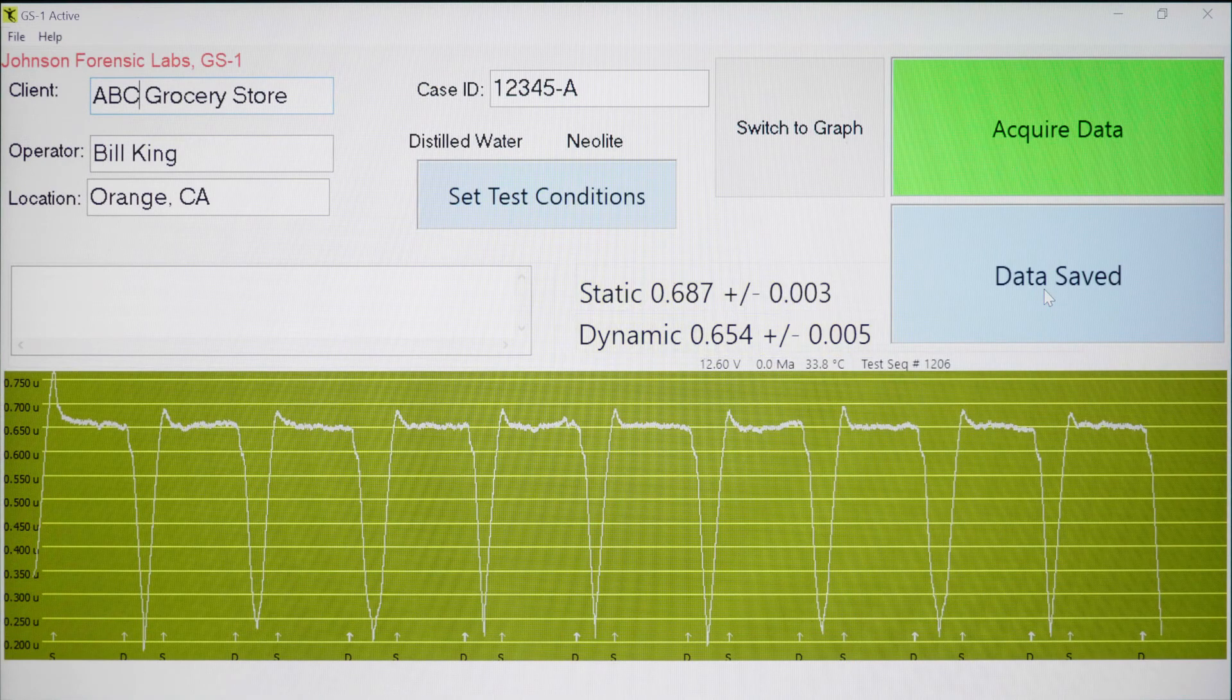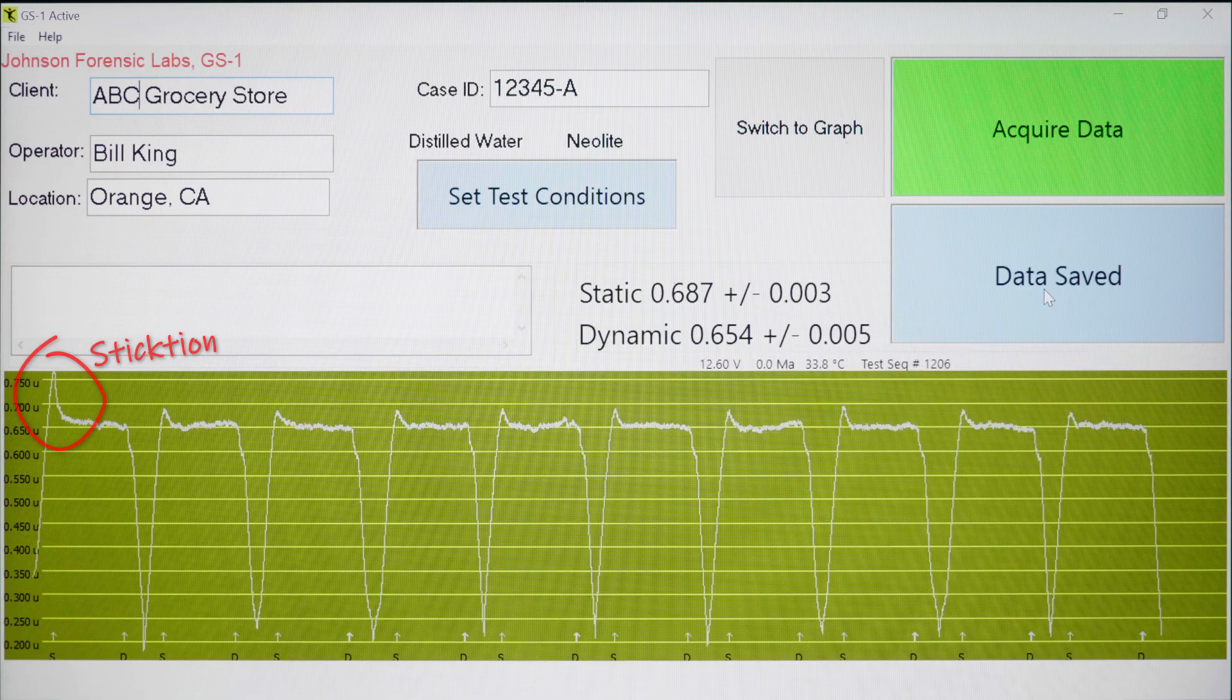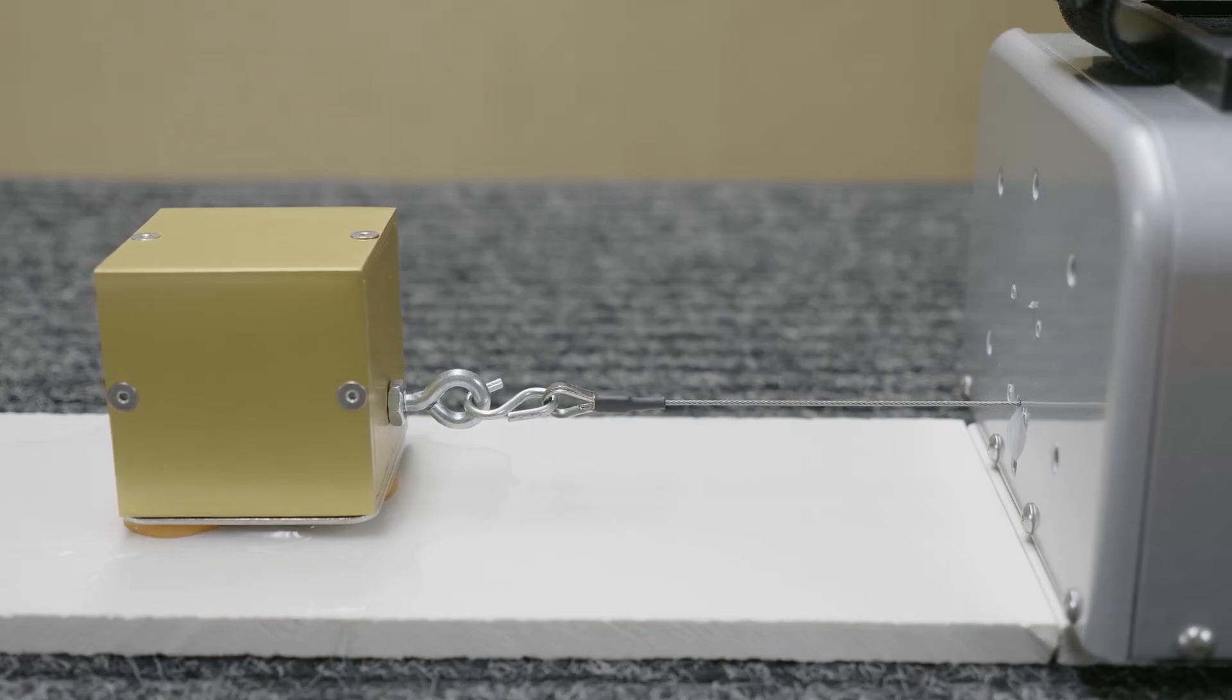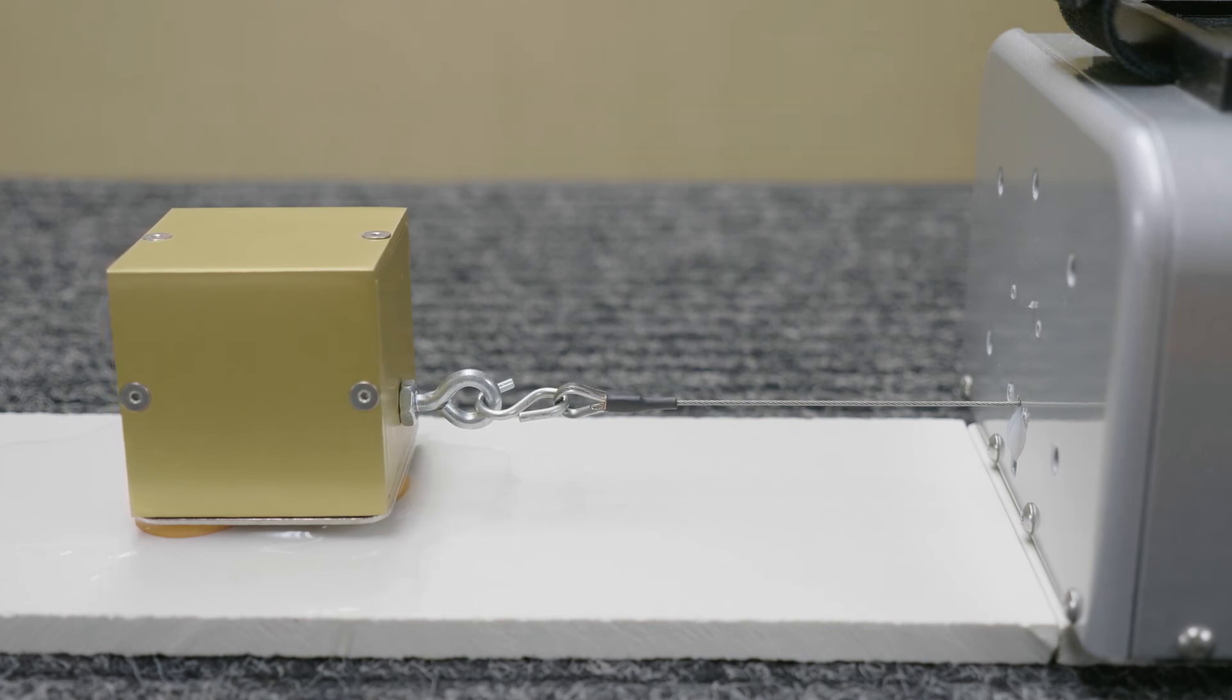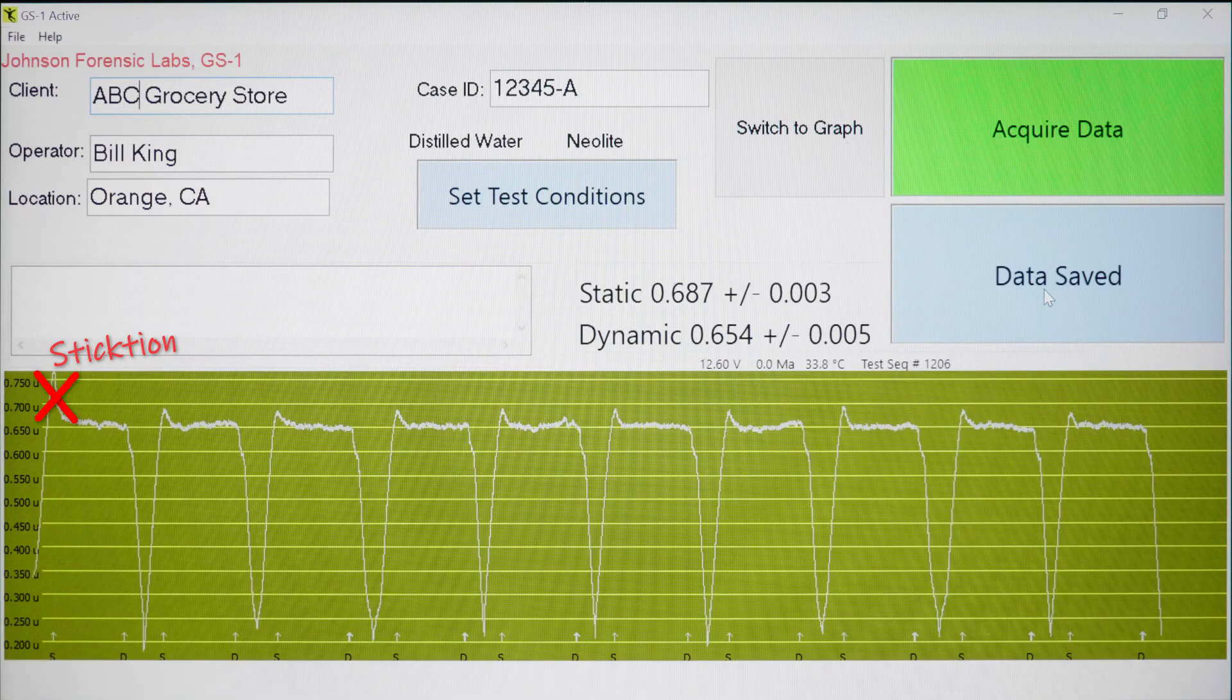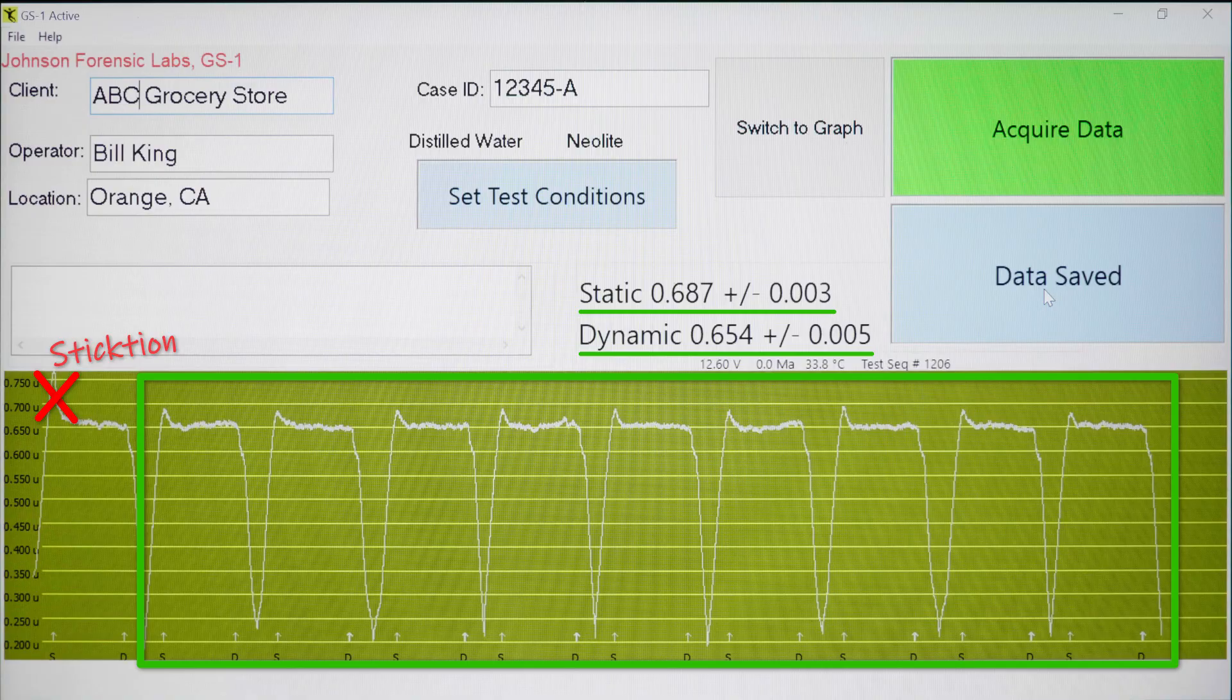The initial measurement of stiction is a critical patented feature which no one worldwide has ever been able to duplicate. Stiction results in extra-surface bonding, which is time-dependent. The longer contact is maintained, the greater is the bonding effect. Stiction must be eliminated when computing the final average to achieve the most accurate results.